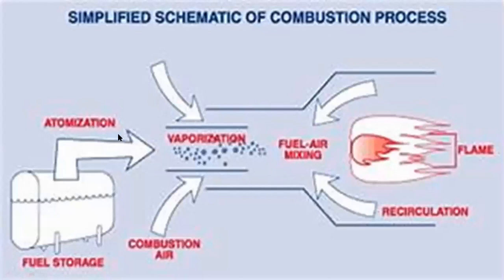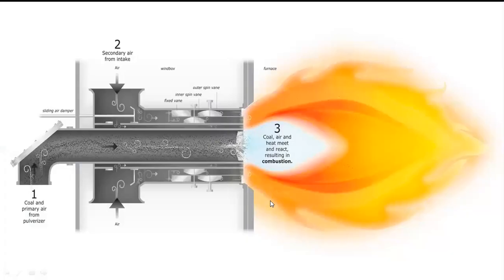Looking at a schematic of a combustion process, you have a fuel storage — it may be a liquid fuel where you are atomizing it. Every fuel can burn only in the vaporized or atomized form. Then you have the combustion air; both are preheated in given quantities. The moment they come together, you have spontaneous ignition in the presence of heat and flame, giving continuous sustenance of the flame with continuous fuel and air. This is a solid fuel-fired burner where we have coal and primary air coming simultaneously — the primary preheated air is transporting the pulverized coal. Then you have secondary air coming through the annulus of the burner. Coal, air, and heat meet and react, resulting in the combustion heat inside the furnace of a coal-fired burner.